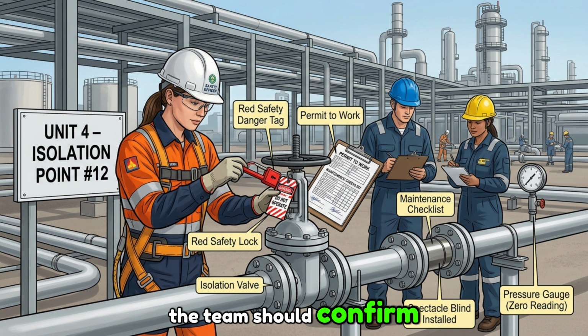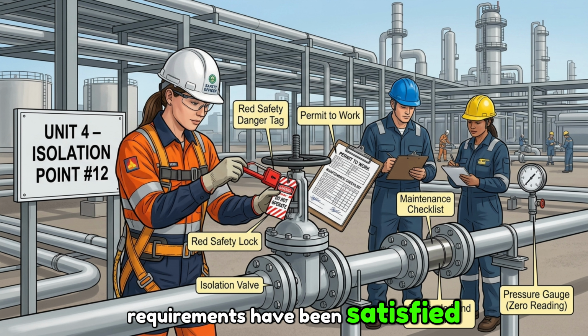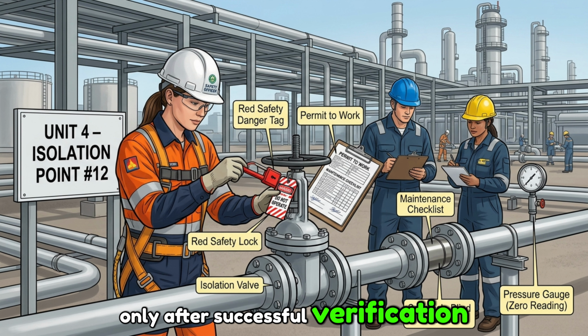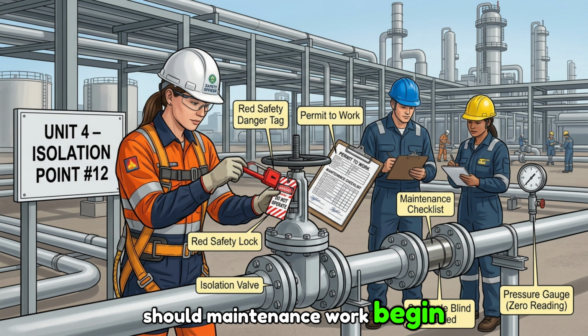The team should confirm that the correct valves have been closed, all pressure has been released, the bleed process has been completed, any required blinds have been installed, spool removal has been carried out correctly, and all permit to work requirements have been satisfied. Only after successful verification should maintenance work begin.